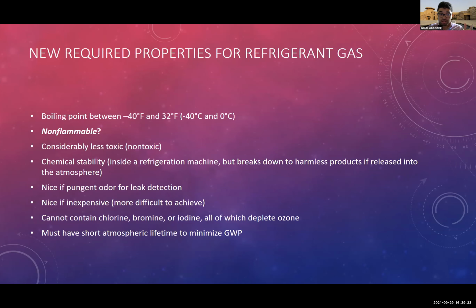If it has a pungent odor, that would be great, because then we would have human leak detection. When it's released into a room, I can detect that there is a refrigerant leak and act accordingly, like open a window, open the door, flush the indoor space, and so on. It would be great if it's inexpensive, and it should not contain chlorine, bromine, or iodine, because these are all ozone depleting substances, and it must have a short atmospheric lifetime to minimize GWP.